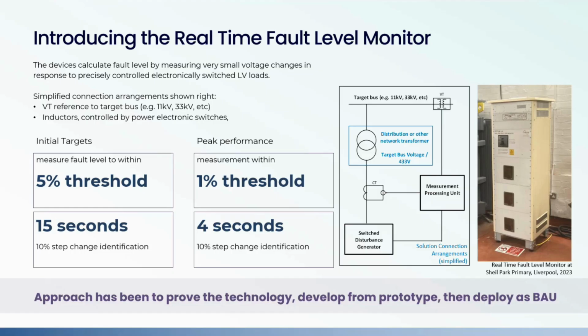In terms of the KPIs that we set for this project, our initial targets were to be able to measure fault level to within a 5% threshold and identify a 10% step change in fault level within 15 seconds. What we mean by that is normally fault level is around the same value for a given network topology, but if we switch the network and change network topology, that can result in a step change in the fault level, and we need to be able to identify that quickly as well, which is more complex than it sounds, because we're also capturing multiple measurements and making sure that we filter out noise. We have to distinguish between real step changes and other things that are happening in the voltage waveforms.